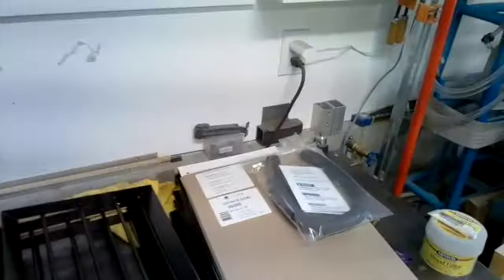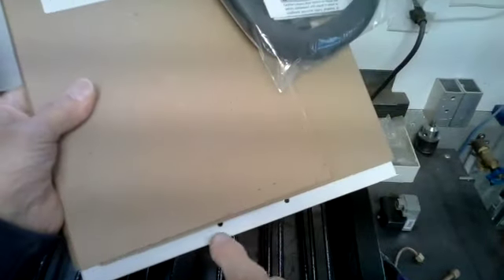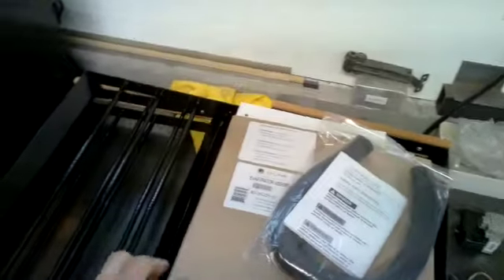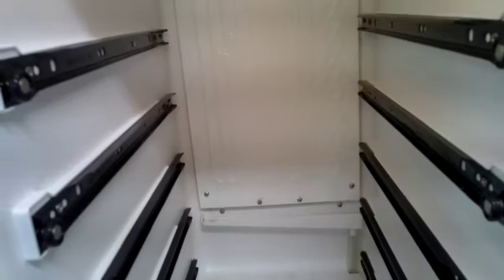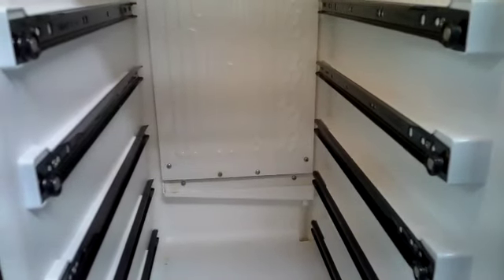And also another option is to use this evaporator plate here, which is for a U-Line. It's the same size, you just have to modify it a little bit and drill an extra hole here on the corners to mount it. The thermostat bolts here like the other, and the only other difference is that the suction line only has one line coming out because the cap tube runs through the suction line. It comes out and goes in there, so that's not a problem. We can still make that work. So we're going to first try to find the leak, and if the evaporator plate is leaking, we can fix that because it's made out of aluminum and we can weld aluminum. So stand by and let's get started.